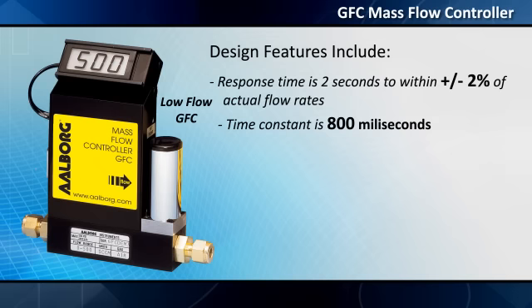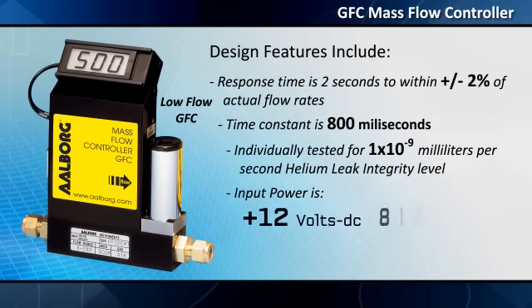GFC mass flow controllers are individually tested for 1×10⁻⁹ milliliters per second helium leak integrity level. Input power is +12 volts DC up to 800 milliamps, or +24 volts DC up to 650 milliamps.